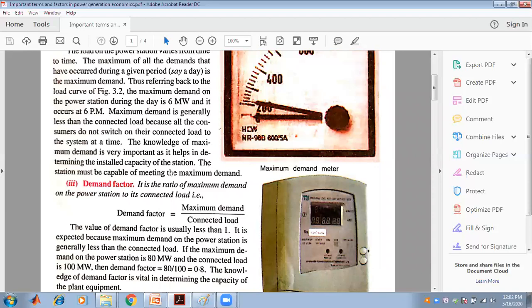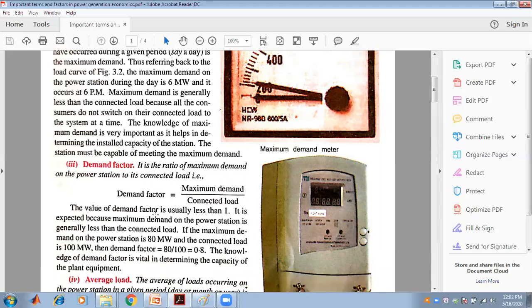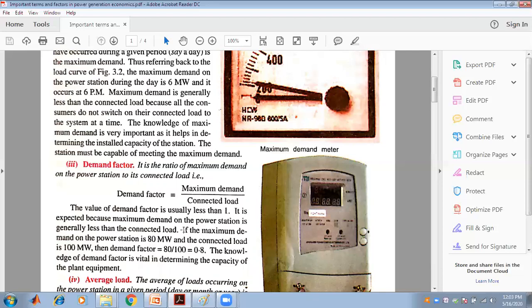The demand factor is the ratio of the maximum demand on the power station to its connected load. The value of the demand factor is usually less than 1, because the connected load is the summation of all connected loads, among which one is the maximum. For example, if the maximum demand of a power station is 80 MW and the connected load is 100 MW, the demand factor is 80 divided by 100, which is 0.8. Knowledge of the demand factor is vital in determining the capacity of the plant equipment.